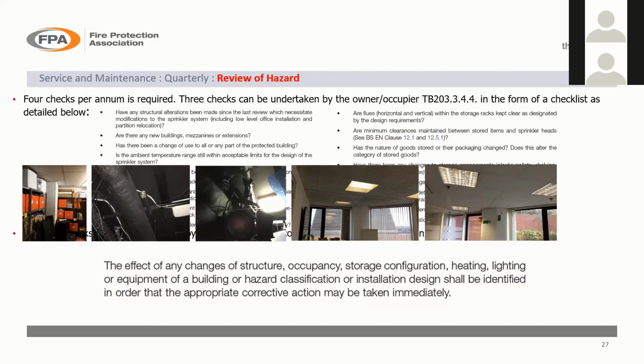It should also have been pointed out by the sprinkler contractor going in and doing a quarterly review of hazards. Just have a look and say you've got a partition there which is blinding these heads. He might not have been aware that that partition had gone in, but certainly the building user would. And if the building user had been trained in what the sprinkler system was there for, he might have been able to say, we're going to put a partition up, do we need to relocate the sprinklers? Because they would probably have relocated lighting and other things, and doors and all the rest of it to accommodate it. Sprinklers also need to be considered when you do that.